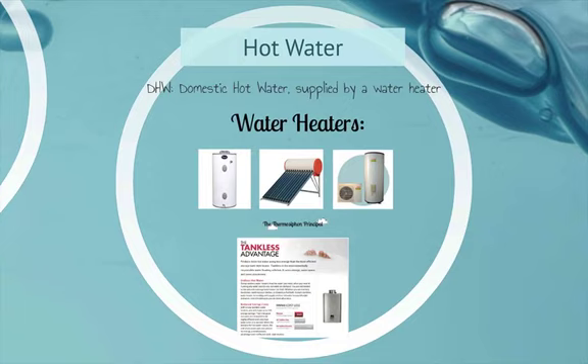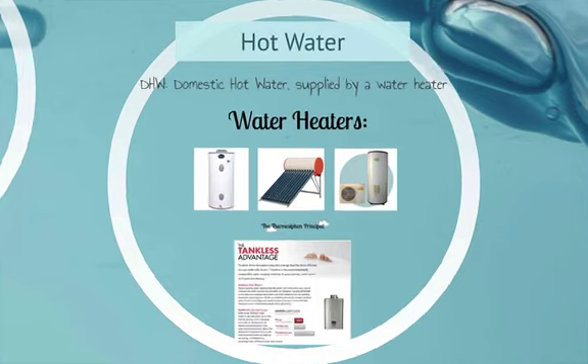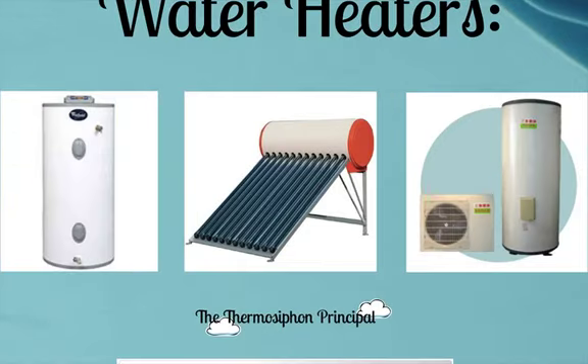All right, so we'll talk a little bit about hot water. DHW, domestic hot water, is water that is basically heated by some sort of water heater. There are various types of water heaters. What you see on the left is basically the standard, most common storage tank water heater. Residential and small commercial buildings usually use these, and they're typically centrally located so that they don't have very long runs to each of the fixtures. They typically have 20 to 80 gallon capacities and can be heated by gas, propane, fuel oil, or electricity. Electricity is going to be the most expensive way to heat the water.